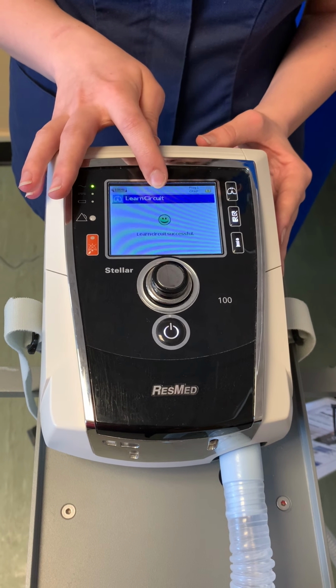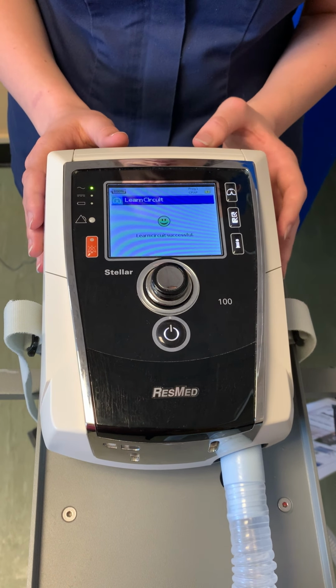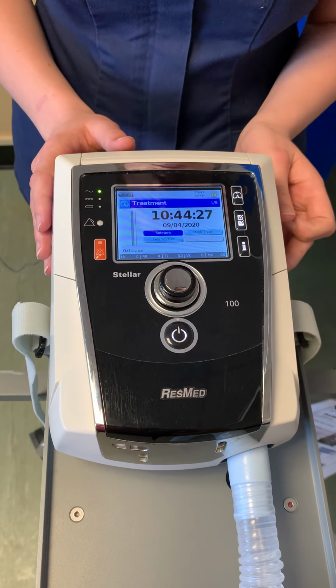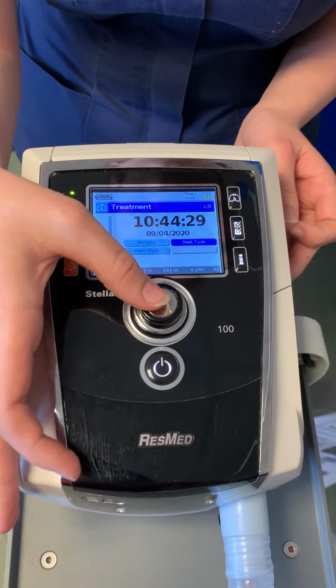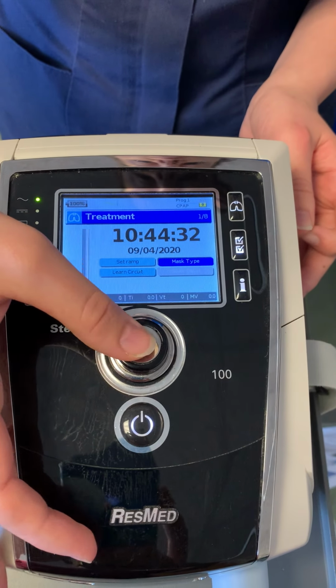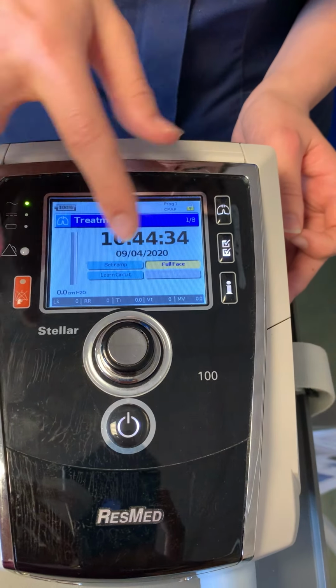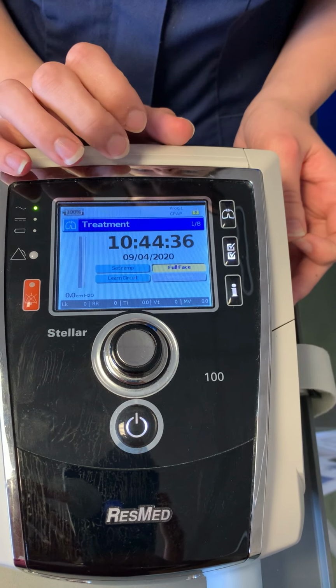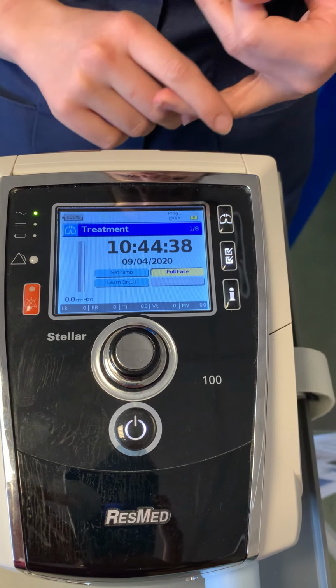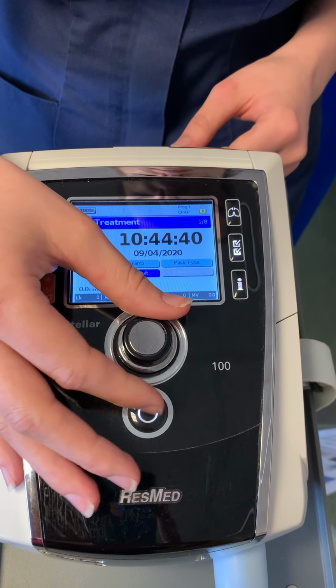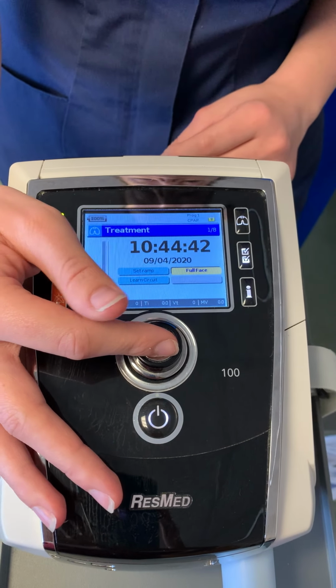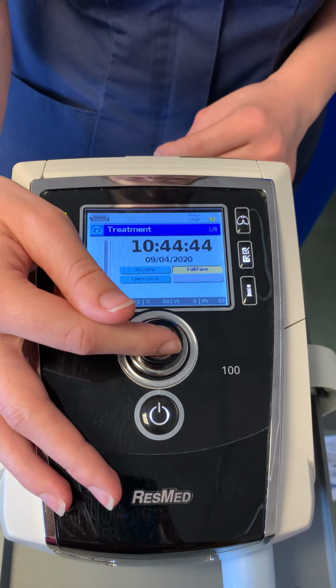Okay, so it's come up with a happy face, which means it's safe to use and we can now use the ventilator tubing. The first thing you can do is check your mask type. You move this spinny thing here, click on it, and it says full face. We should only be using full face. There are settings for paediatric and trachea. However, in an adult setting, we should only be using the full face mask unless a consultant has said otherwise.